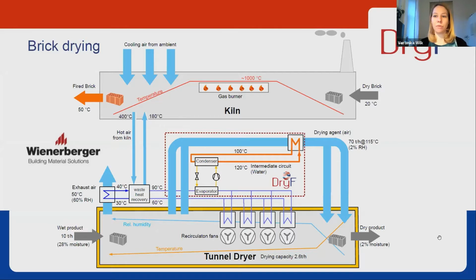So they enter the kiln at 20 degrees C and they're heated to 1000 degrees C. And in the final part of the kiln, there's cooling air coming in, and then the product is leaving at 50 degrees C. And both steps are energy intensive for brick production. And we integrated the heat pump into the drying process. There's also a heat recovery system already in place. It's a thermal driven heat pump, making use of the waste heat from the kiln and also using the humid exhaust gas from the dryer. And with this thermal driven heat pump, a water cycle is heated to 90 degrees C, and this is transferring the heat into the tunnel dryer with heat exchanger surfaces that are located within the tunnel.